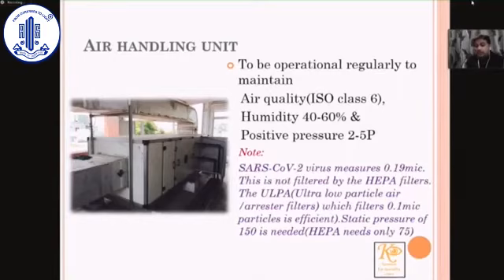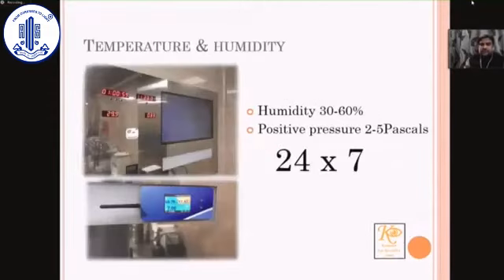And if you're going to change your filters to ULPA, you need to change your blower, because you need to have a static pressure of 150, which is not attained with your traditional blowers. You have to upgrade your blower. And it is also a good practice to install UV lights inside the chamber in both the pre-filter areas.